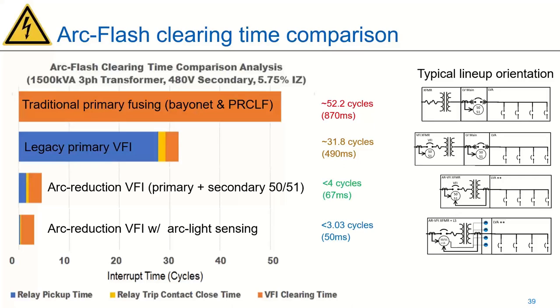And this is part of the difficulty and what IEEE 1584 was trying to overcome. I think there's probably work to be done on the true dynamic nature of faults, but looking at the enclosure size and electrode configuration and how that factors into the calculations, that's going to try to account for some of that dynamic nature, and it's going to treat it more like a real fault rather than making assumptions, say, of a fault from A to B phase. In reality, that's probably going to start A to B and propagate to A to B to C until it's all over the place until it gets cleared. So the enclosure size and electrode configuration values that you're using in 1584 help dictate and smooth out that variability.